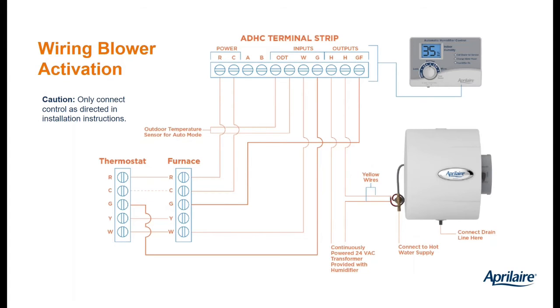Starting at the automatic humidistat, so starting at the top of the diagram, you can see we've got power, R and C. That's just going to go to R and C inside the HVAC system. In this diagram, inside the furnace. So you're just going to piggyback another wire to R and another wire to C on the furnace. Okay, let's go back up to the automatic humidistat. Let's skip a few terminals and let's go under inputs. You see W. We're just going to add another wire and piggyback that W at the humidistat to W down at the furnace. So we've just grabbed maybe 3 conductor wire, whatever you have handy, and we've piggybacked in an R and a C and a W. Very simple, very straightforward. So far, it's just like wiring up another thermostat, really.